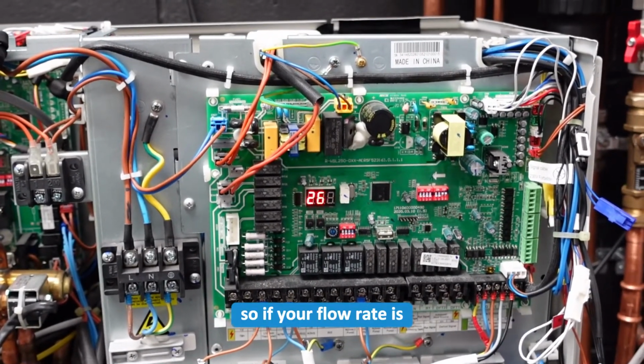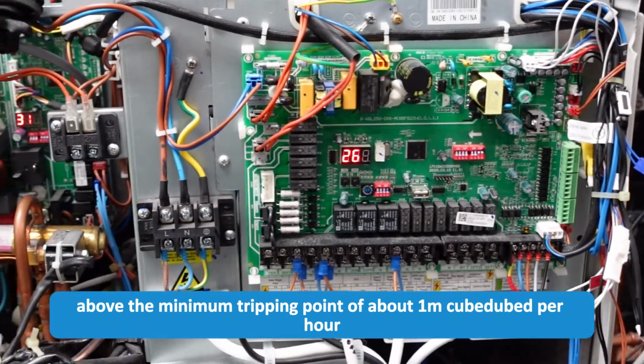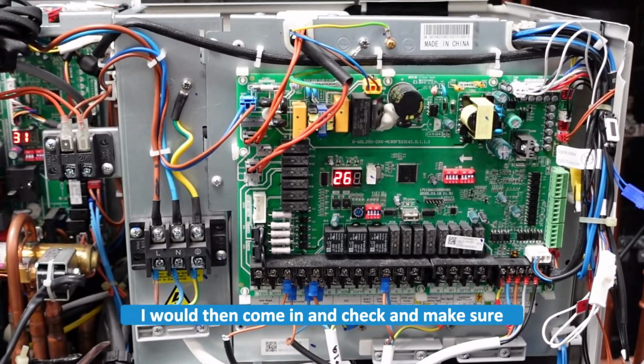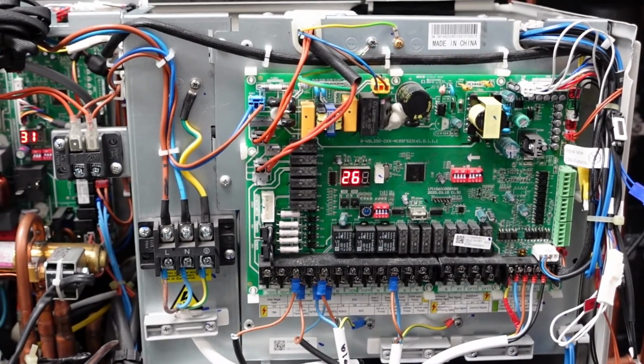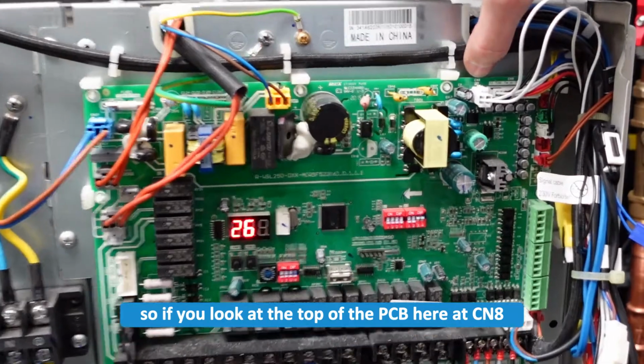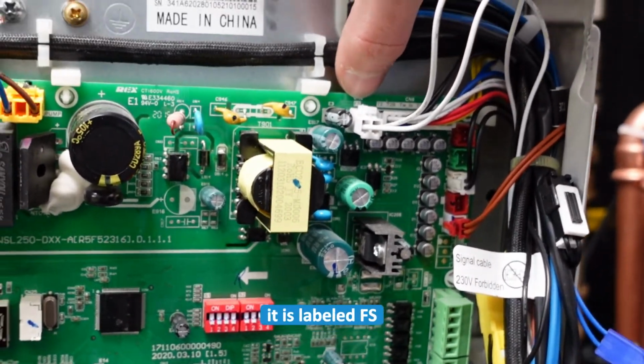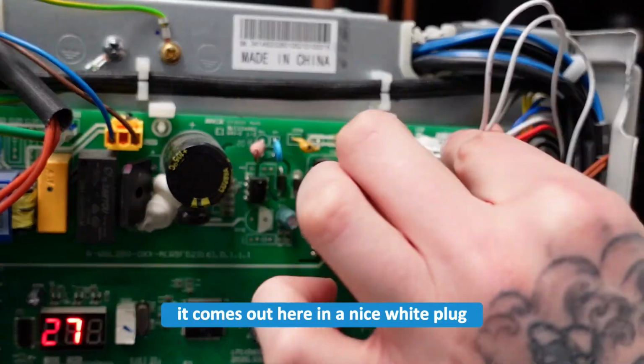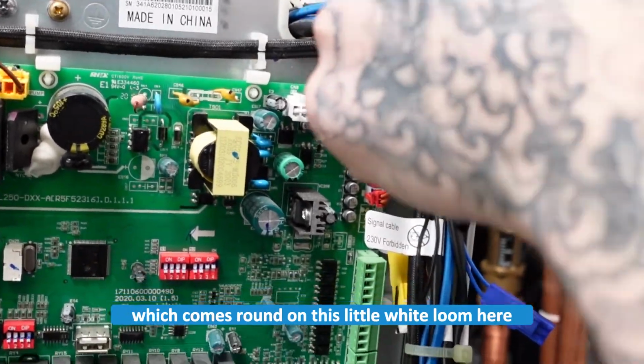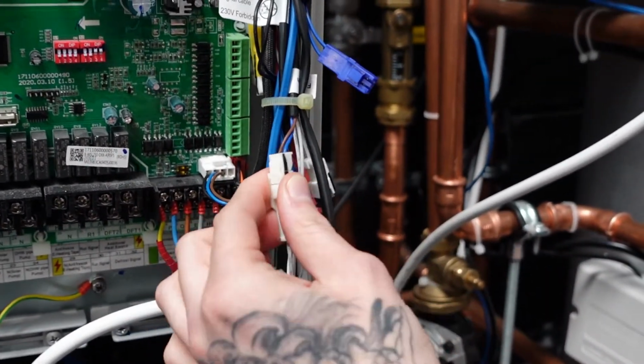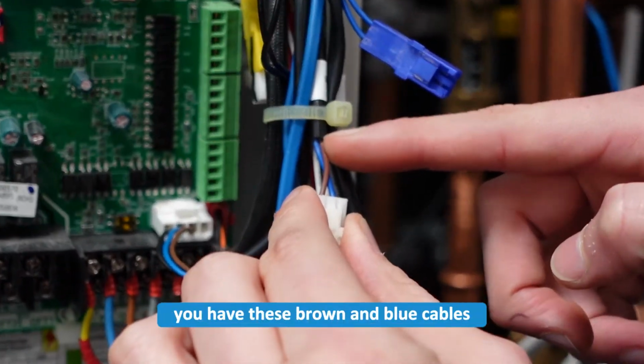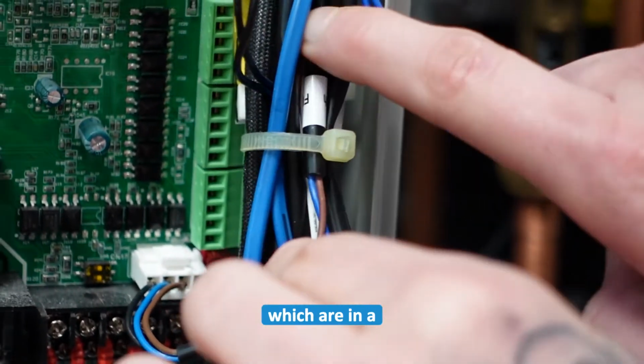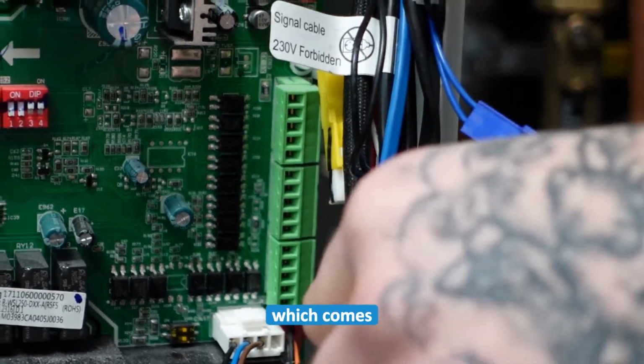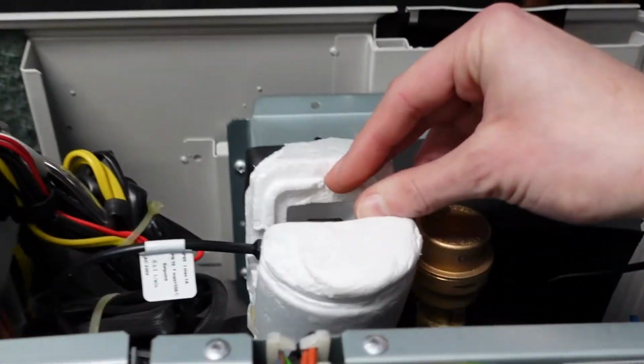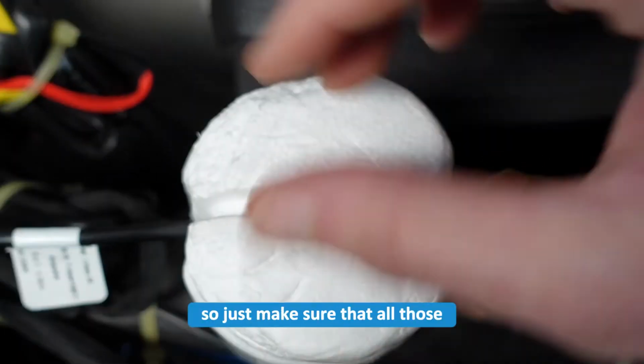So if your flow rate is above the minimum tripping point of about 1 meters cubed per hour, I would then come in and check and make sure that our flow switch is all connected in properly. So if you look at the top of the PCB here, at CN8 or connector 8, it is labeled FS, which stands for flow switch. It comes out here in a nice white plug, which comes round on this little white loom here to this other white connector block. And then on the other side of the white connector block, you have these brown and blue cables, which are in a black shielding, which comes up to the flow switch, which is in the top of the unit here, as you can see. So just make sure that all those connection points are all firmly in and secured.